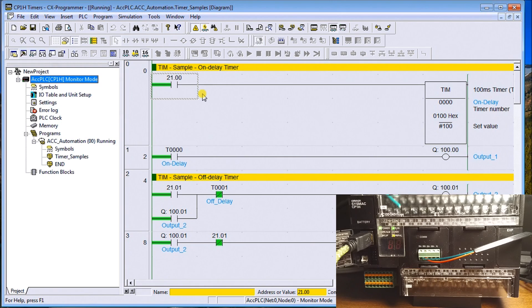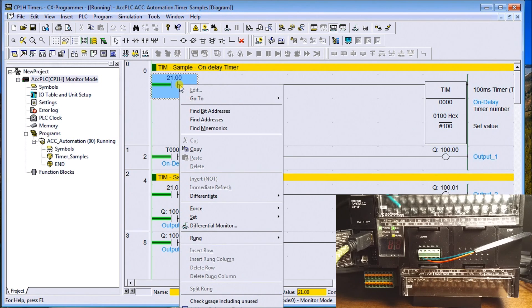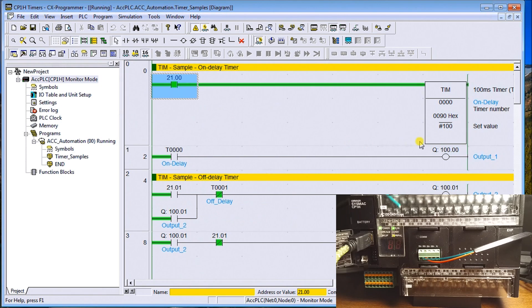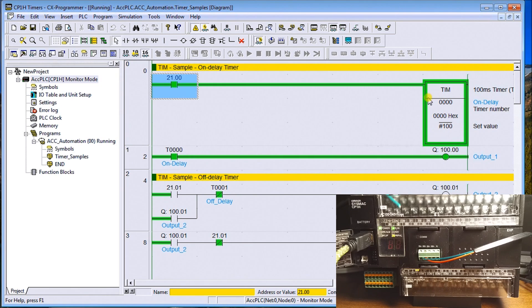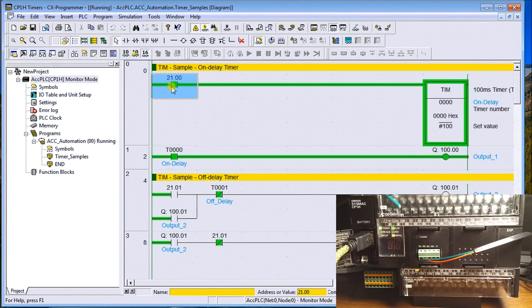I'll energize this first input and set that on. When I do, the timer starts timing down. We have a set value of 100, and because it's a 0.1-second time base, 100 represents 10 seconds. As soon as that finishes timing it turns on the timing contact, which then turns on my output — you can see it coming on right on my PLC.